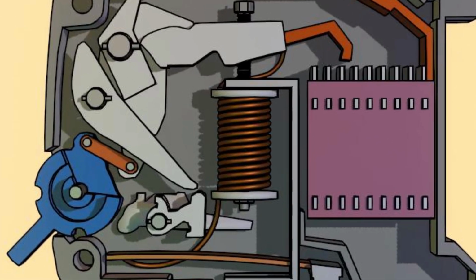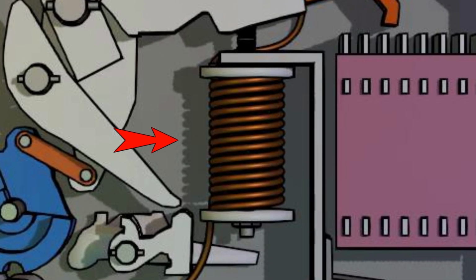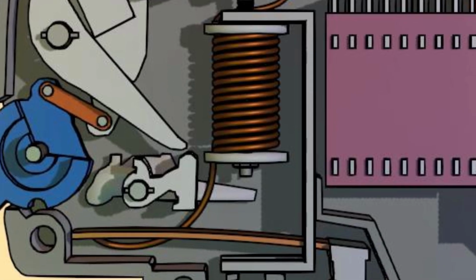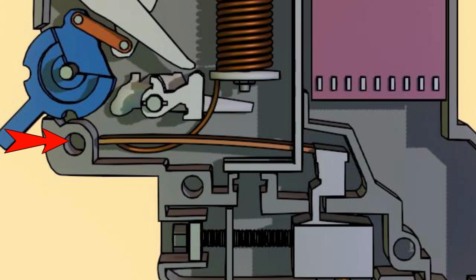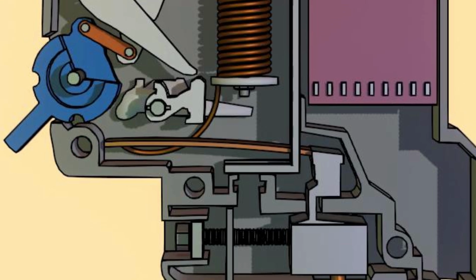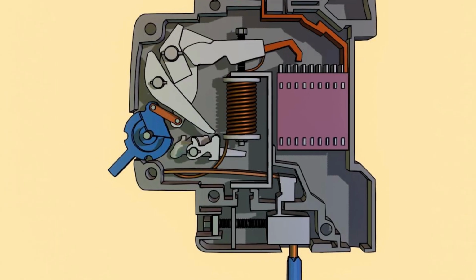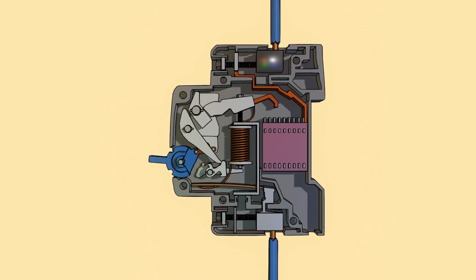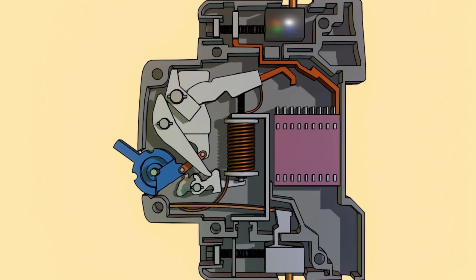One is an inductor connected in series with the circuit so that the entire current can flow through it. Another is a bimetallic thermo element that is also connected in series with the circuit. When any short circuit arises, the current crosses a threshold value, the magnetizing force of the coil becomes so high that it will be able to move the plunger, which will strike the tripping mechanism lever to trip the circuit breaker, or MCB. The other arrangement is the bimetallic strip, which bends during overheating. That means during overloading condition. When it bends, it pushes the mechanism to trip the breaker.